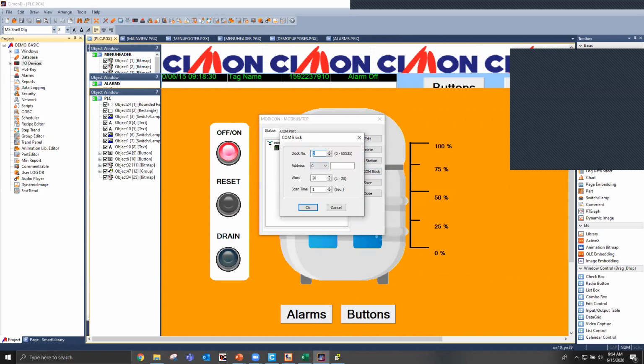You know your registers, so the block number is not necessarily important, but for the address, we talk to the 0, 1, 3, and 4 addresses. Those are the only addresses that we talk to in terms of Modbus. You come over here and type in a 0, and then it's the first 20 words. So it'll do from 00000 all the way up to 00020, or 00019. It'll do the first 20 words of this register. Since we're referring to 0 and 1, those are only the bits, but we'll consider those words when we're talking about Modbus. If I actually wanted to talk to the word registers, I'd pick 3 and 4, obviously.